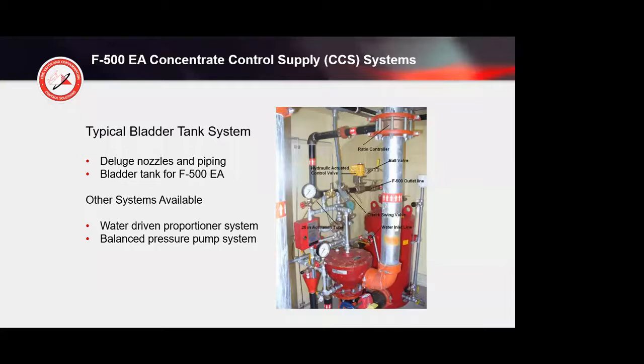The reason it got us in the business was because Ansul sold the tank. The contractor installed the tank, put the agent inside the tank, and we got a call 6 months later that the agent has eaten up the glue seams of the bladder tank. What are you going to do about it? So the bottom line is we have an encapsulator agent. Inside those bladders are glued seams. There's 3 components, a top piece, a bottom nozzle piece, and the center piece, and those are all glued together. And our agent encapsulates hydrocarbons. So over a short period of time, about 6 months to a year, it encapsulated the glue and the bladder came apart. So it was at that point we said, okay, we need to get into our own bladder system with our own bladder that's been tested, that's compatible with our agent.